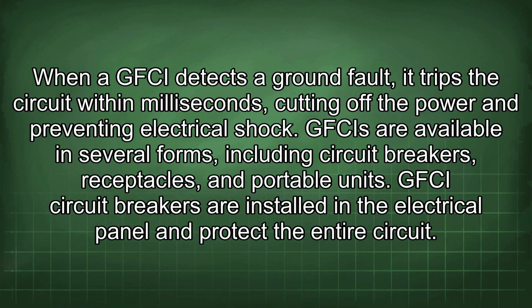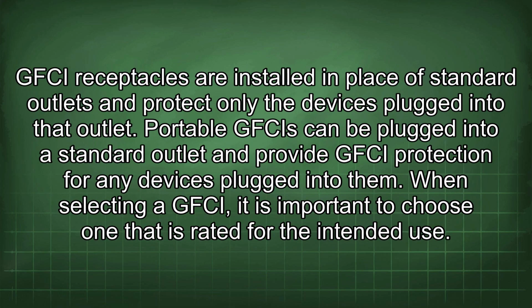When a GFCI detects a ground fault, it trips the circuit within milliseconds, cutting off the power and preventing electrical shock. GFCIs are available in several forms, including circuit breakers, receptacles, and portable units. GFCI circuit breakers are installed in the electrical panel and protect the entire circuit. GFCI receptacles are installed in place of standard outlets and protect only the devices plugged into that outlet. Portable GFCIs can be plugged into a standard outlet and provide GFCI protection for any devices plugged into them.